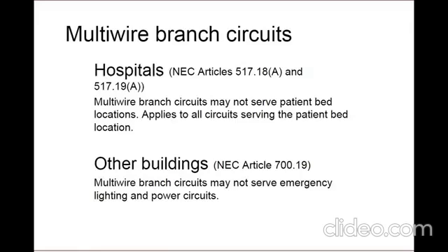The final difference I'll mention is with multi-wire branch circuits. Article 700.19 prohibits multi-wire branch circuits from serving emergency lighting and power circuits. Article 517 contains requirements that do not allow the use of multi-wire branch circuits in general care and critical care spaces. This applies to all branch circuit wiring regardless of system, including normal power. The rationale is that disconnecting means for multi-wire branch circuits are required to simultaneously disconnect all ungrounded conductors. This could present a hazardous situation where lights or receptacles at a patient bed location are interrupted unintentionally.